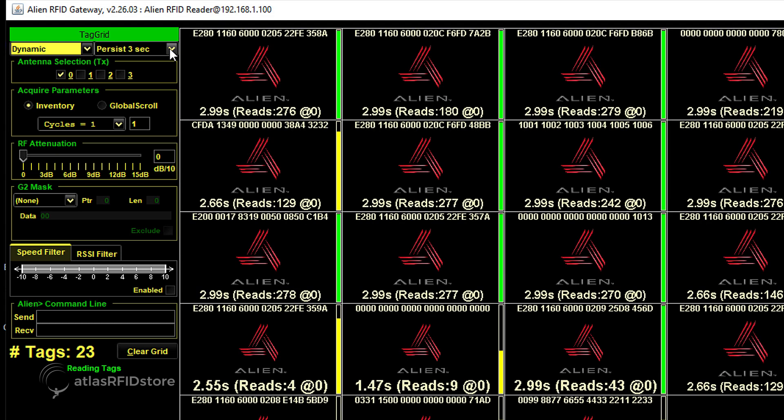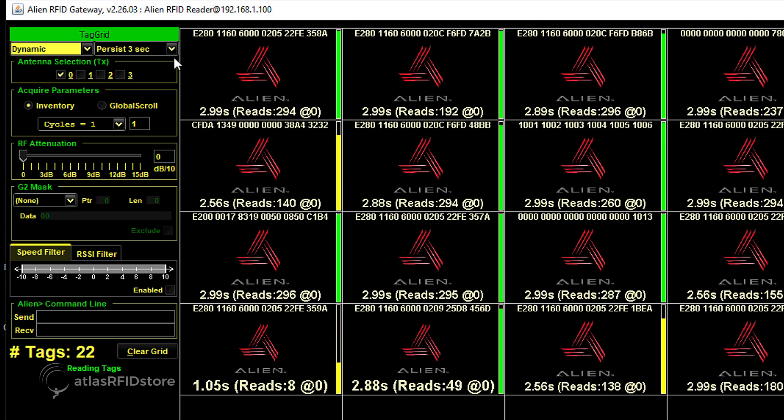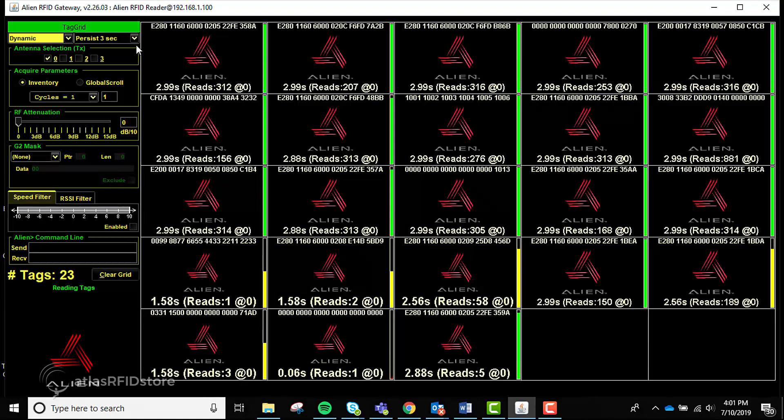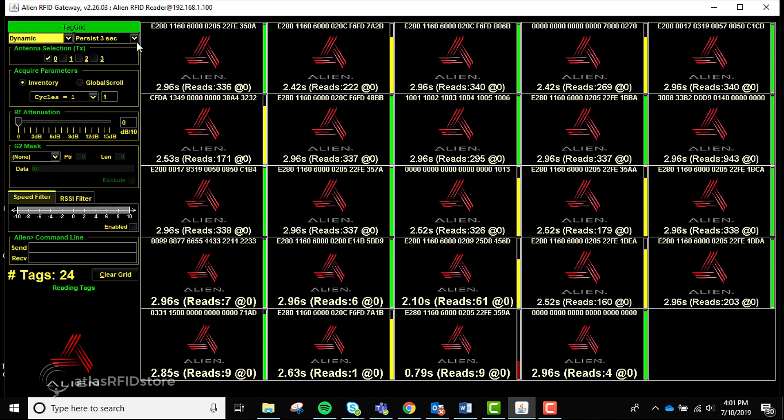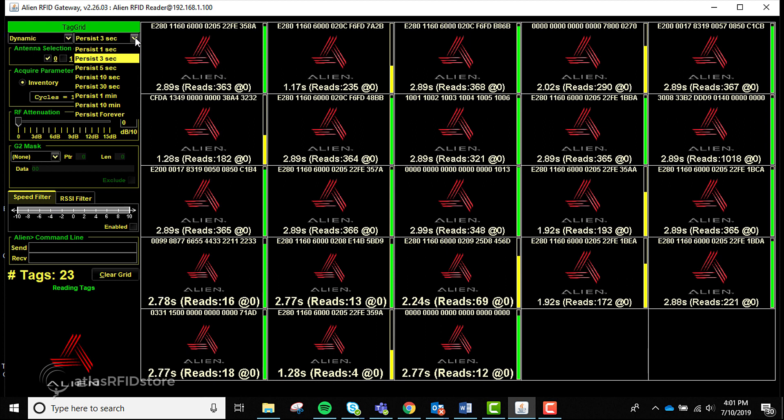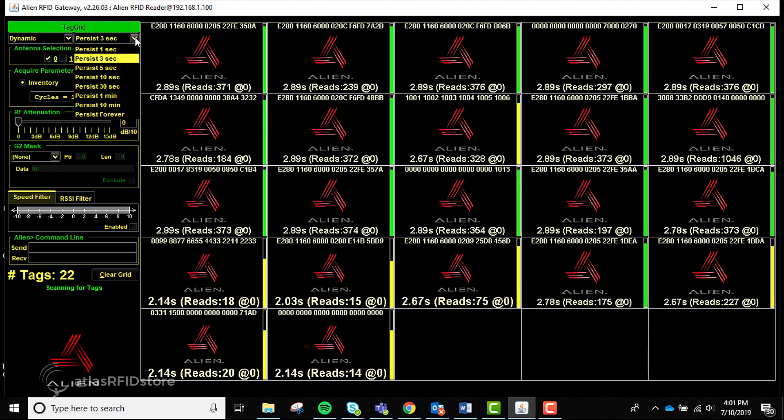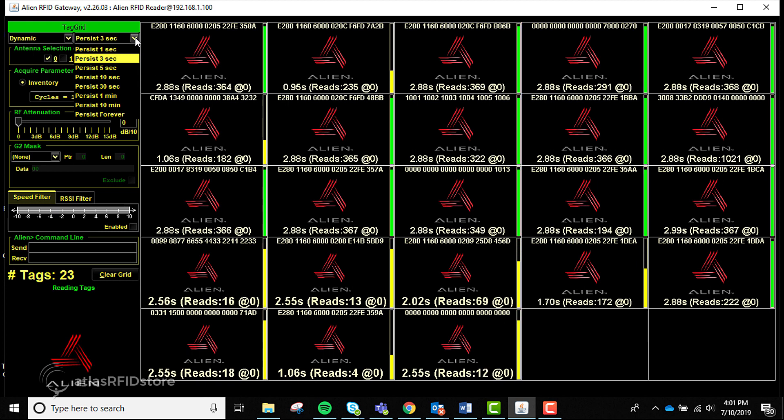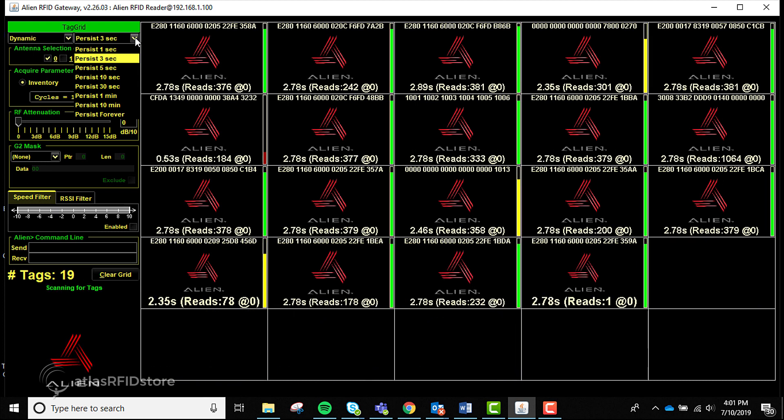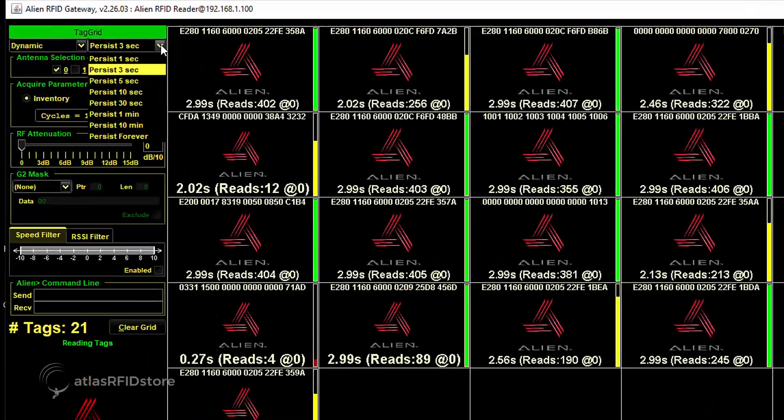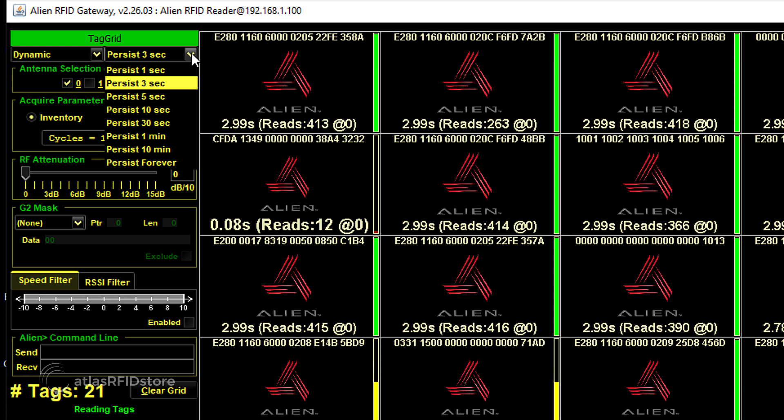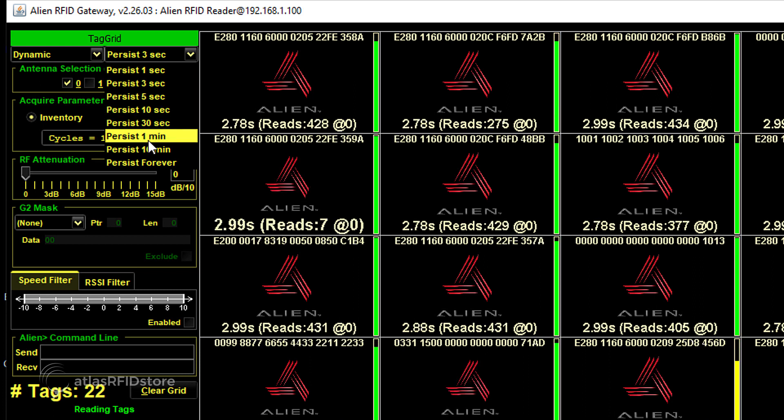The next drop-down menu is Persist Time. The Persist Time is the amount of time a tag's data remains on the tag grid after it is read. As you can see, the Persist Time is constantly counting down from a preset time. With this menu, there are a few different options to choose from for setting that time. When the countdown reaches 0, the tag will disappear from the tag grid display until it is read again. If it remains in the read area, the tag will stay on screen and reset the Persist Time and restart the countdown. For this demonstration, we will toggle the Persist Time from 3 seconds to 1 minute to show the difference between the two settings.